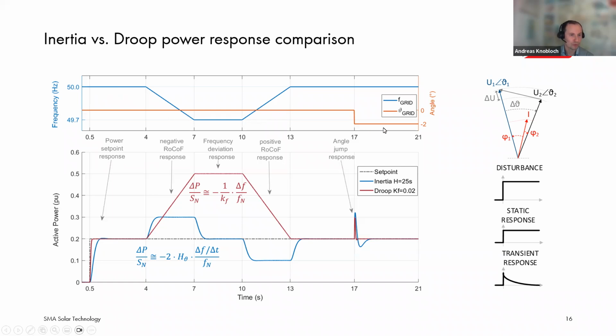And the red curve describes the grid angle. So the angle of this voltage vector U2, this is the grid voltage vector, while U1 with the angle is the inverter side voltage vector. And in the lower plots, you see the active power response. The dotted line is the active power reference, and you see the behavior at power set point response, so at reference response behavior.